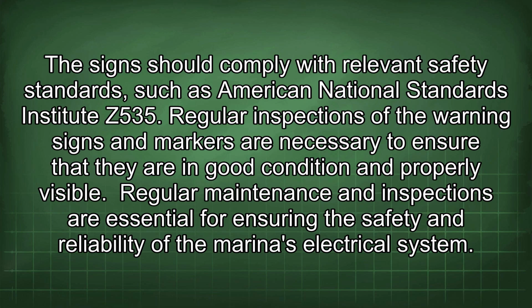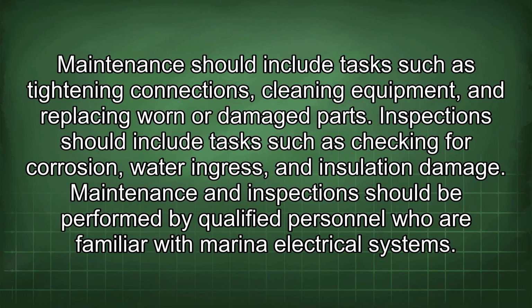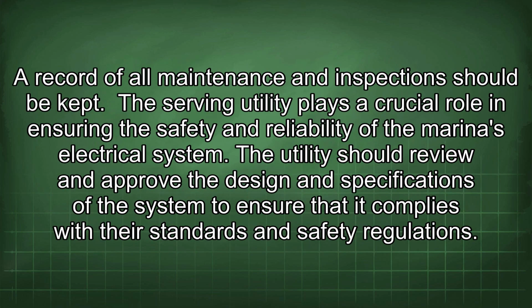Regular maintenance and inspections are essential for ensuring the safety and reliability of the marina's electrical system. Maintenance should include tasks such as tightening connections, cleaning equipment, and replacing worn or damaged parts. Inspections should include tasks such as checking for corrosion, water ingress, and insulation damage. Maintenance and inspection should be performed by qualified personnel who are familiar with marina electrical systems. A record of all maintenance and inspection should be kept.